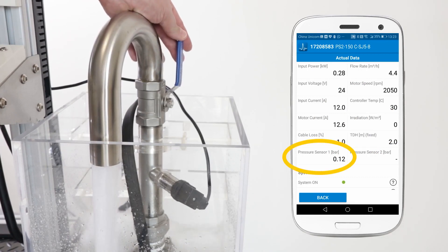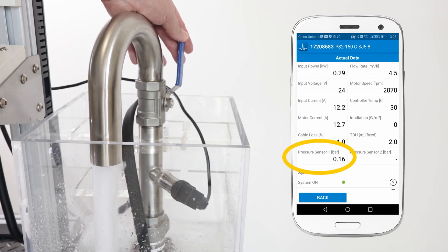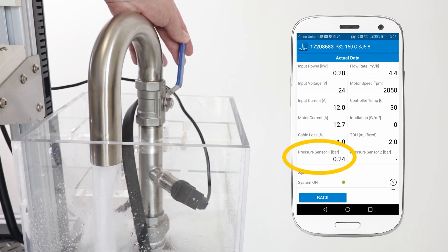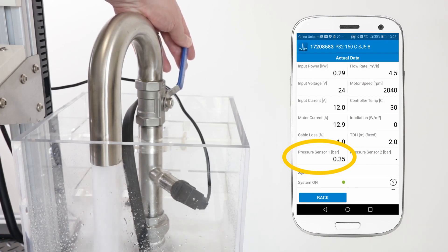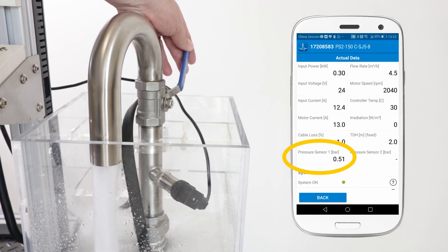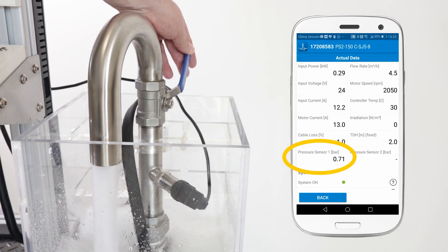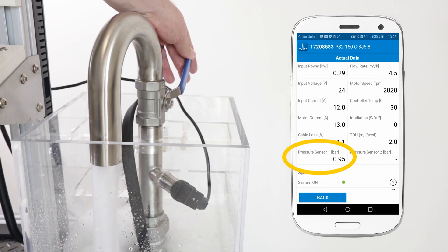I will save that and let's see what happens. So now I go back to actual data, we can watch the pressure sensor 1 reading. As I close the valve, tank is full, the valve opens and the pump switches off.